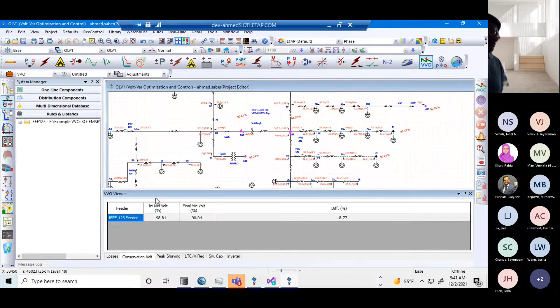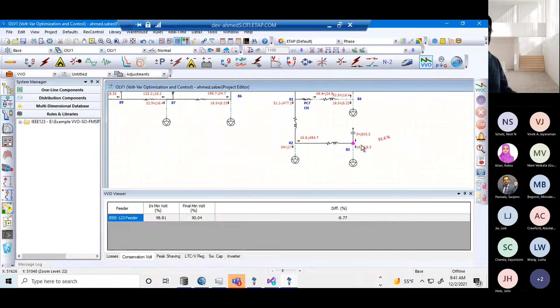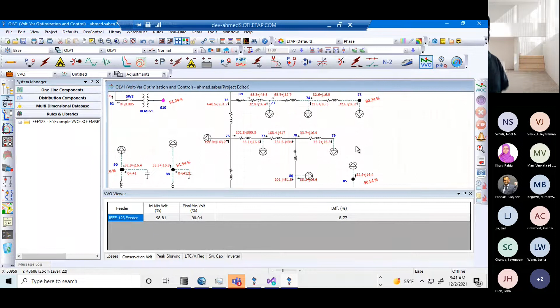Around 20%, that's huge. And you see here the initial voltage is 98%, but now I went to 90%. So you see here the last voltage, maybe it's not big, right? Here you can see voltage is 91, not 90, because some other load or end voltage is already 90 - you see here it's already 90.25. So if you set the limit to 90, this part will be less than 90, maybe 89, so we cannot go to 90 here.